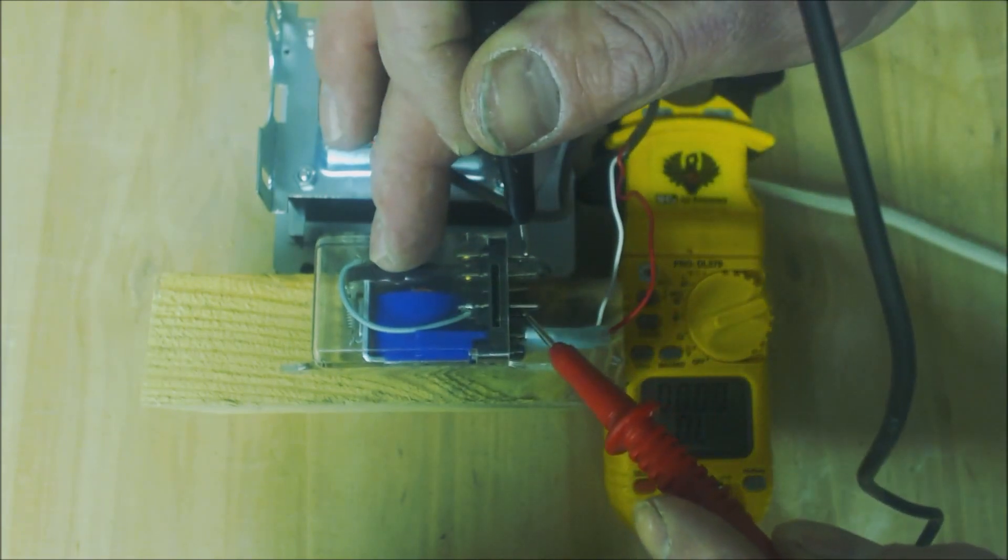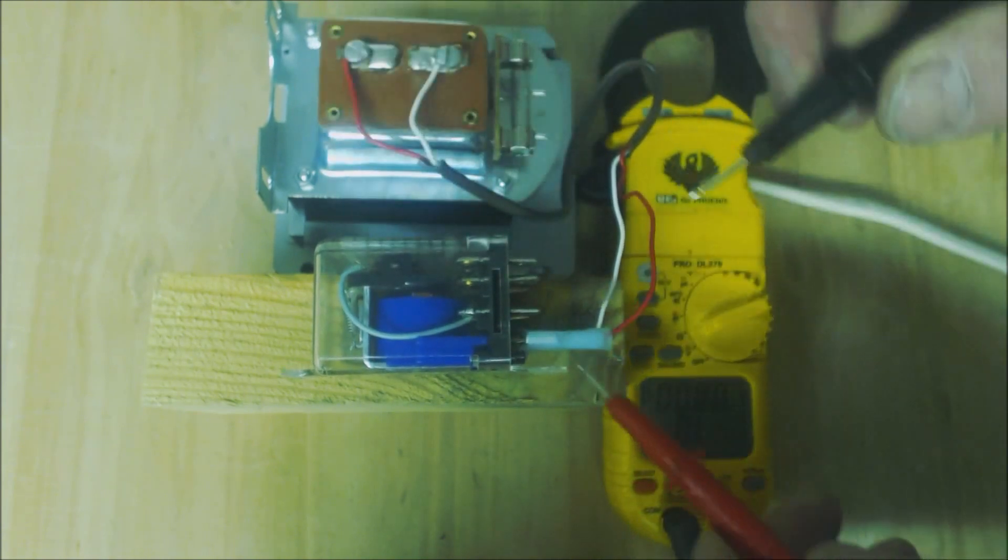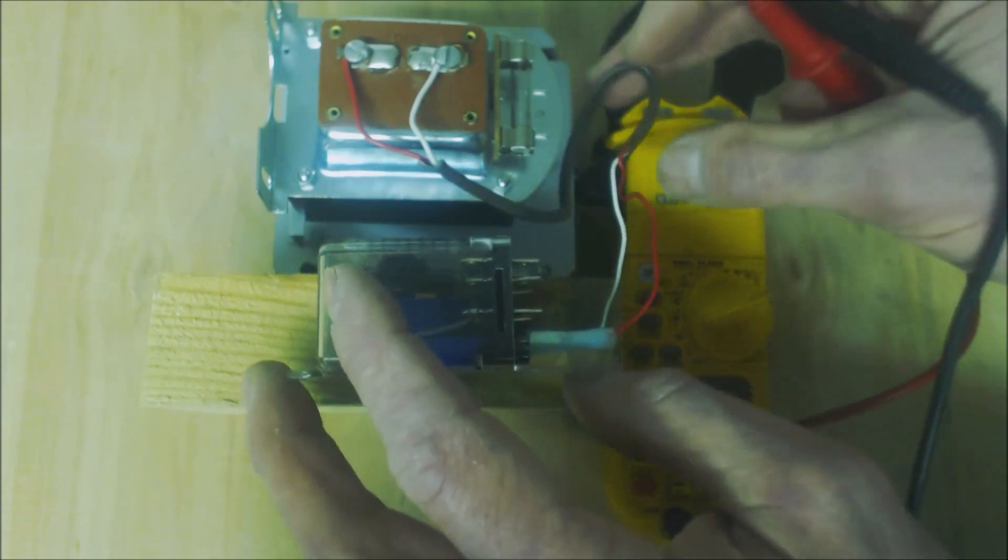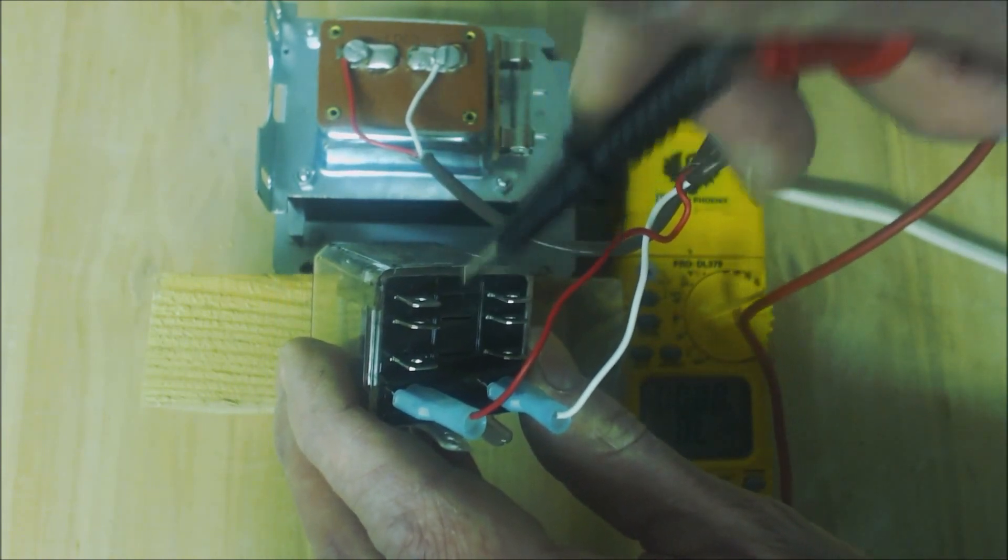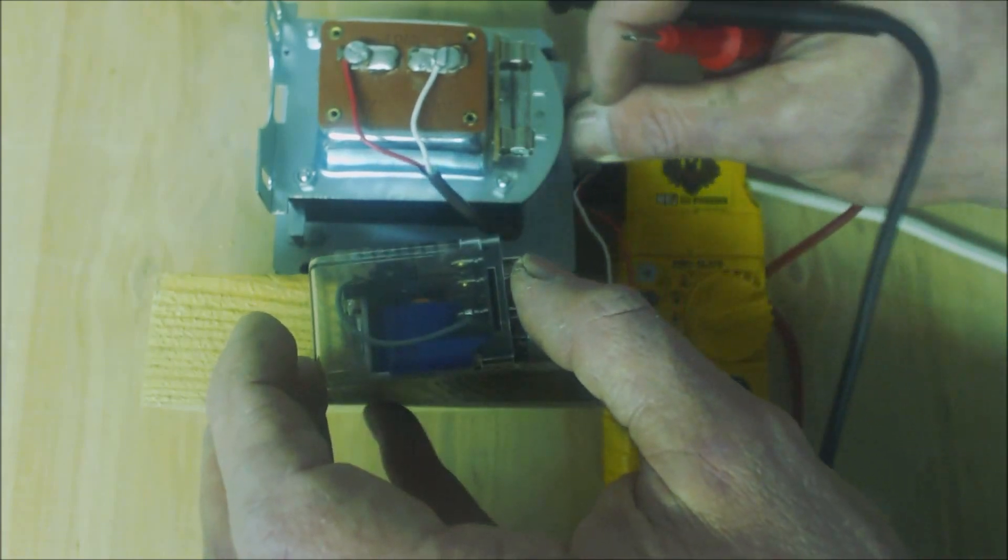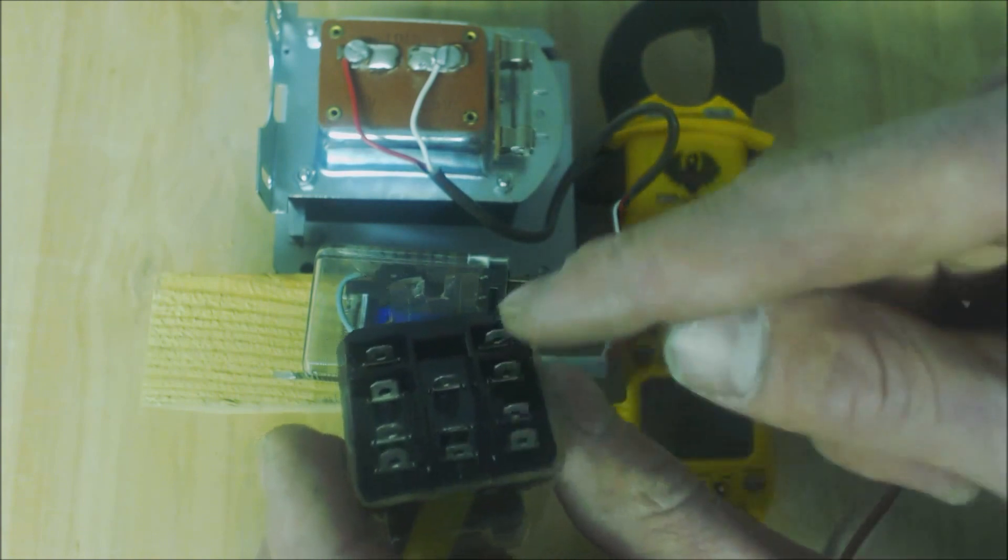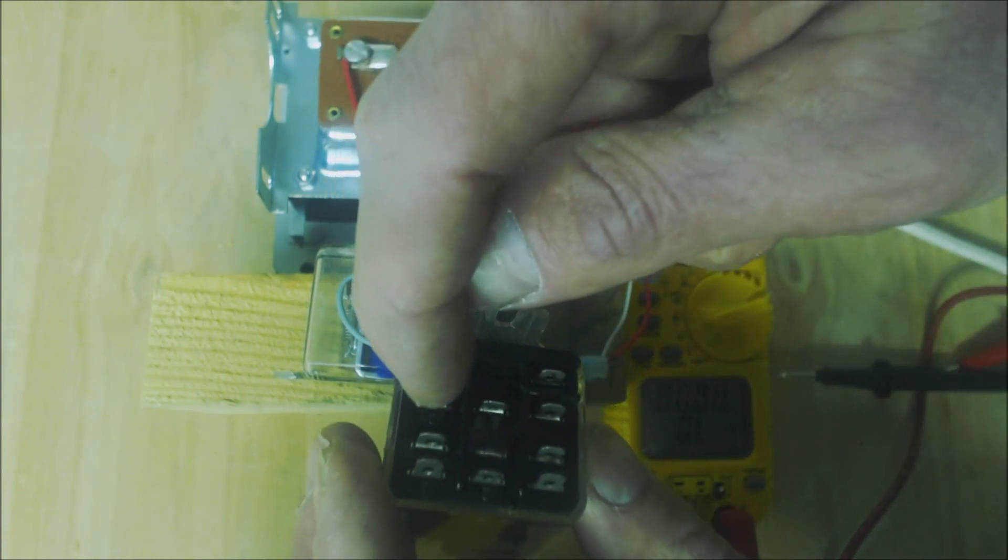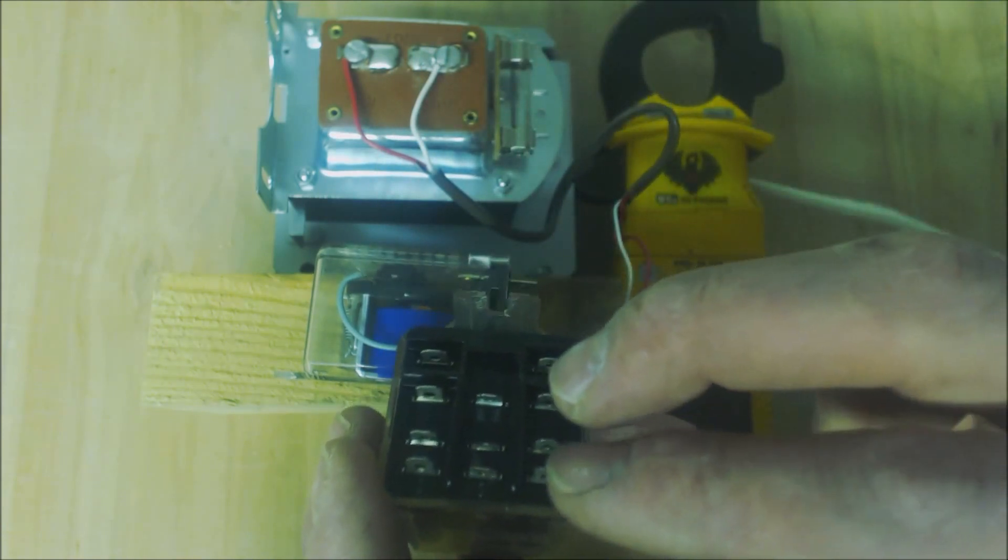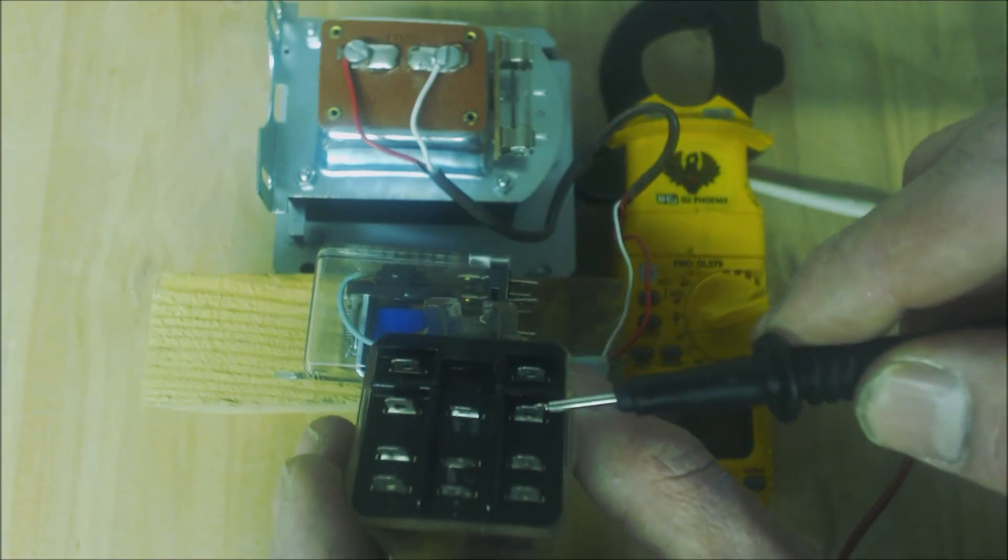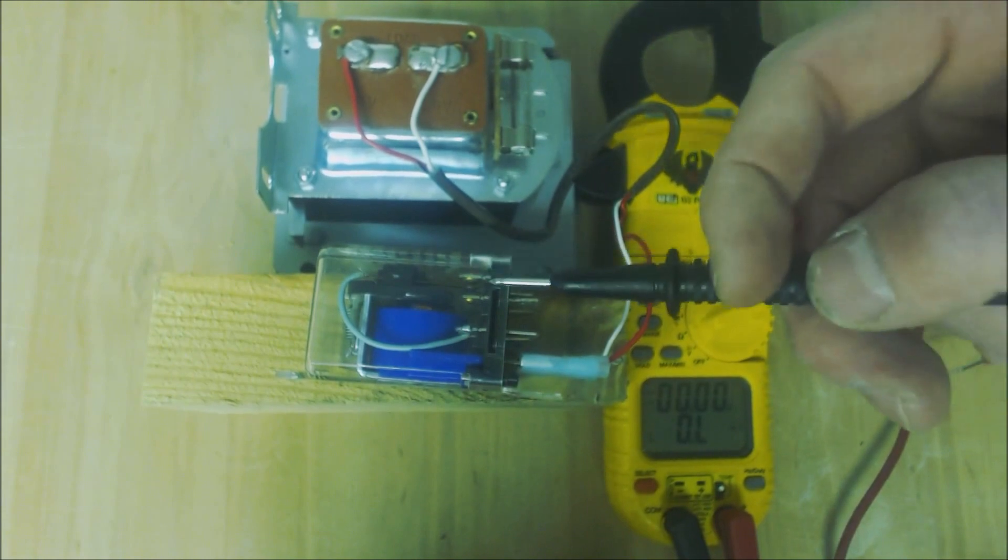That's called the normally closed position, and this is the normally open position. Same thing down here, you have two sets on this one. This one's a 24 volt one. This one right here has three sets of contacts right here and right here. So it's just power in right here, here and here. Your normally closed are the outside ones, and your normally open are here and here.